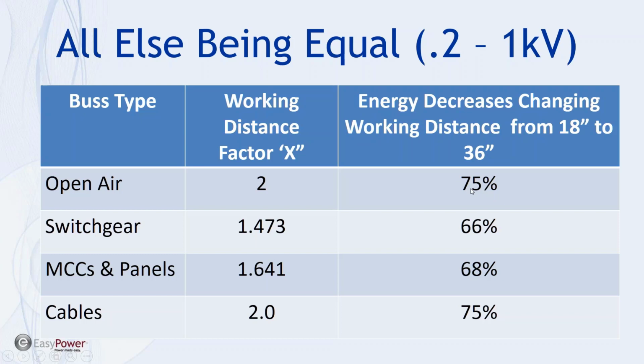75% decrease in the incident energy. In the case of switchgear, that same movement of working distance, we get a reduction of 66%. And in motor control centers and panels, the reduction is 68%. And this can be significant. Again, it's necessary to convey the correct type of panel that we're using.